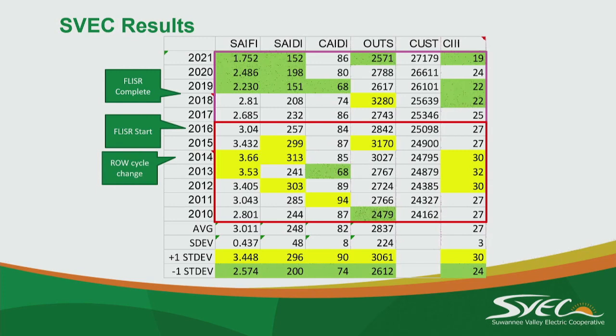And momentaries, do you not count momentaries? We do not. Do any- maybe work, yeah. And what is your momentary, 1 minute, 5 minutes? Our reclose cycle half second on what we call fast trip. We're set up for fuse saving. And then I think we have a 5 and a 10-second reclose and then lockout. Our outage is momentary defined 5 minutes because we're electric co-op, that's IEEE standard of 5 minutes. Anything less than 5 minutes is considered momentary. I think some of the IOUs might fall underneath the 1 minute momentary definition.